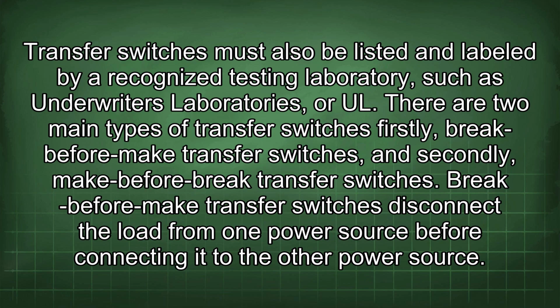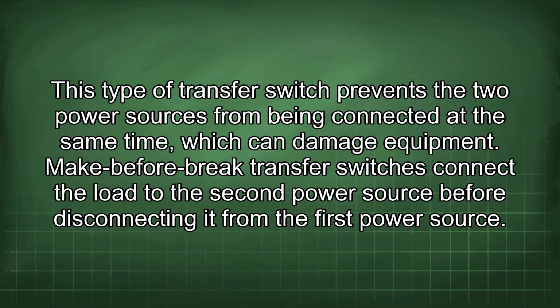There are two main types of transfer switches: firstly, break-before-make transfer switches, and secondly, make-before-break transfer switches. Break-before-make transfer switches disconnect the load from one power source before connecting it to the other power source. This type of transfer switch prevents the two power sources from being connected at the same time, which can damage equipment. Make-before-break transfer switches connect the load to the second power source before disconnecting it from the first power source.